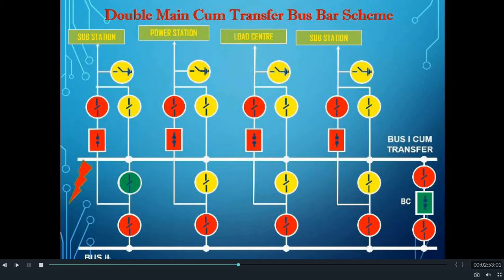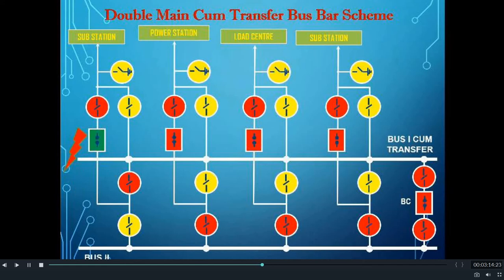In that situation, the substation or the bus bar of the substation will act as a single bus bar scheme. Now let us see how this bus bar scheme works in case of a fault in a circuit breaker. Let us go to the previous condition of feeder number 1 being connected to bus number 2 and all other feeders connected to bus 1 and running normally. In such a case, when there is a fault in the circuit breaker of feeder number 1, the feeder will trip immediately.